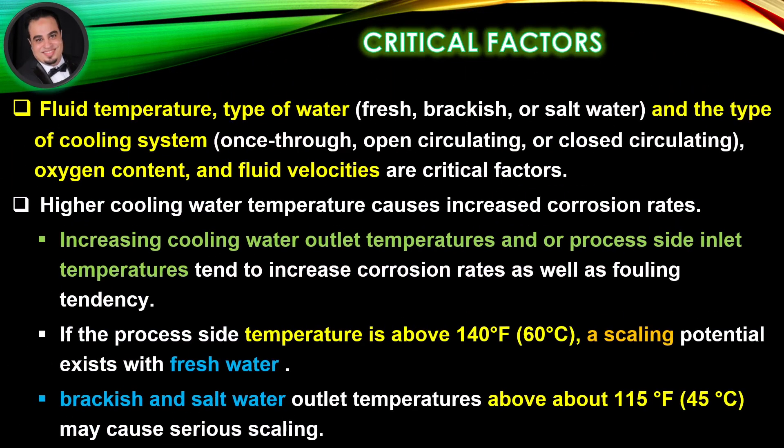Critical factors include fluid temperature, type of water — fresh, brackish, or salt water — and the type of cooling system: once-through, open circulating, or closed circulating. Oxygen content and fluid velocities are also critical factors.